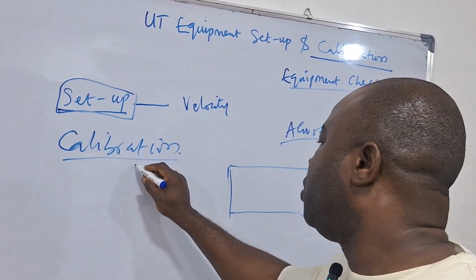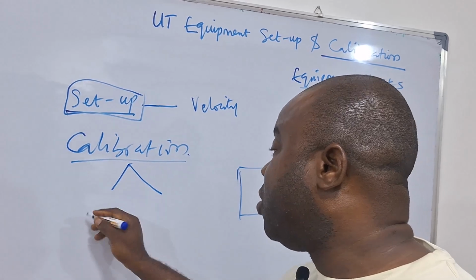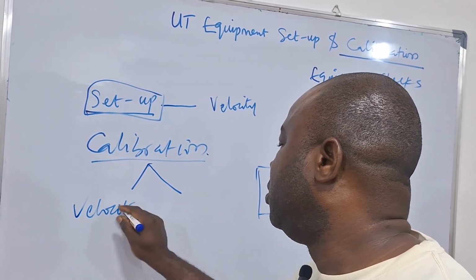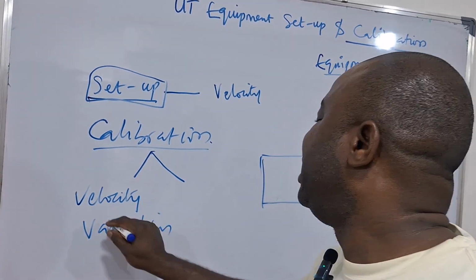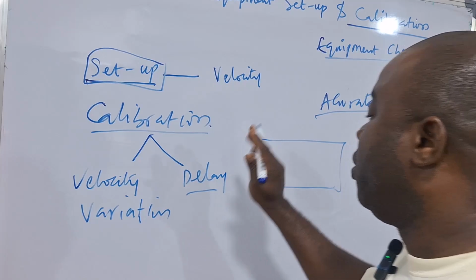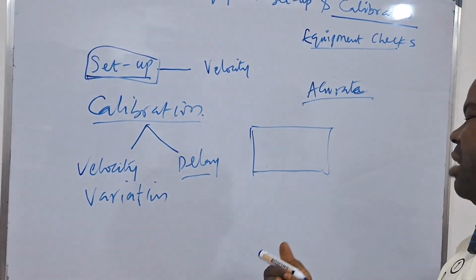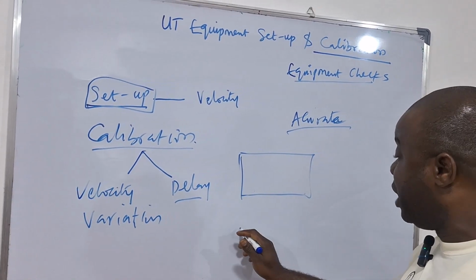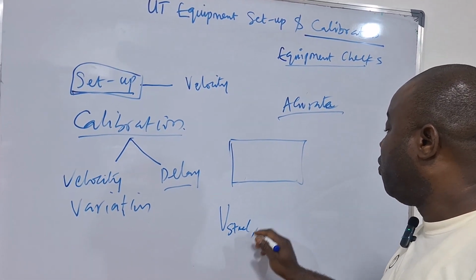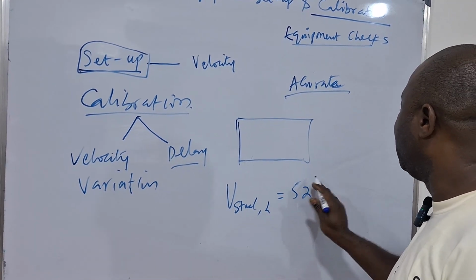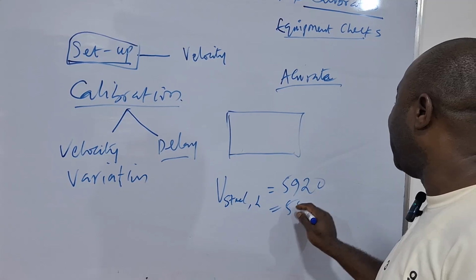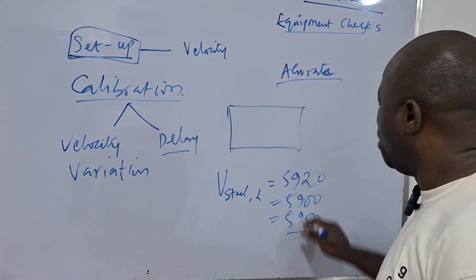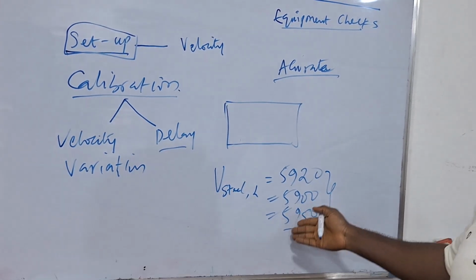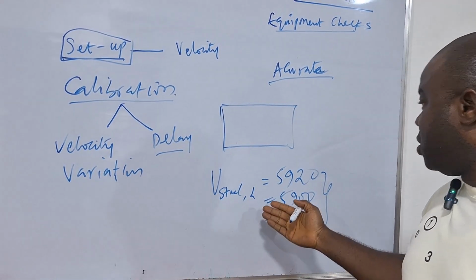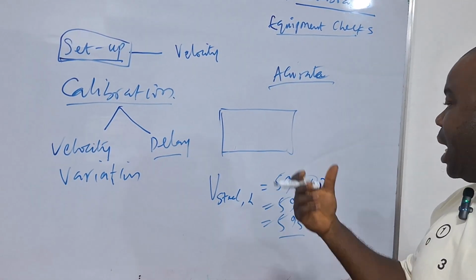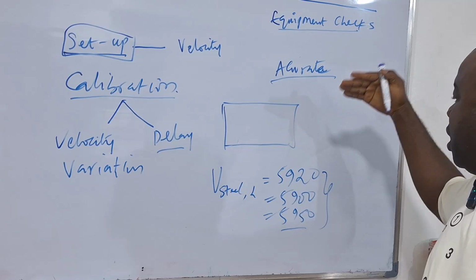The whole essence of calibration is because one, there will be what we call variation in velocity. Then there is also the second issue of what we call the delay. When we say variation in velocity, if you read a couple of UT books, you discover that, for example, let's say for velocity of steel, for longitudinal wave, some books will tell you it's 5920, others will tell you 5900, others will tell you 5950. So it depends. Does that mean these velocities are wrong or one is correct and the other is wrong? Definitely not. Even steel as a material is an alloy of iron and carbon. So you always have this variation in the material constituent.